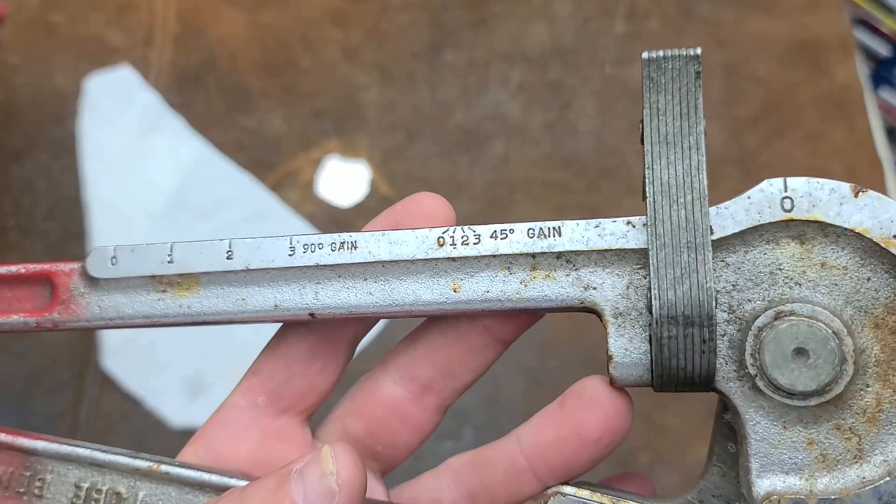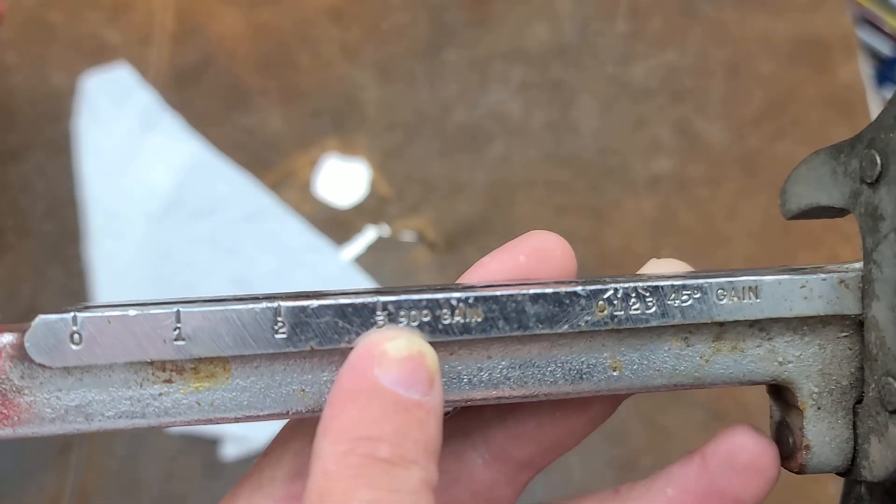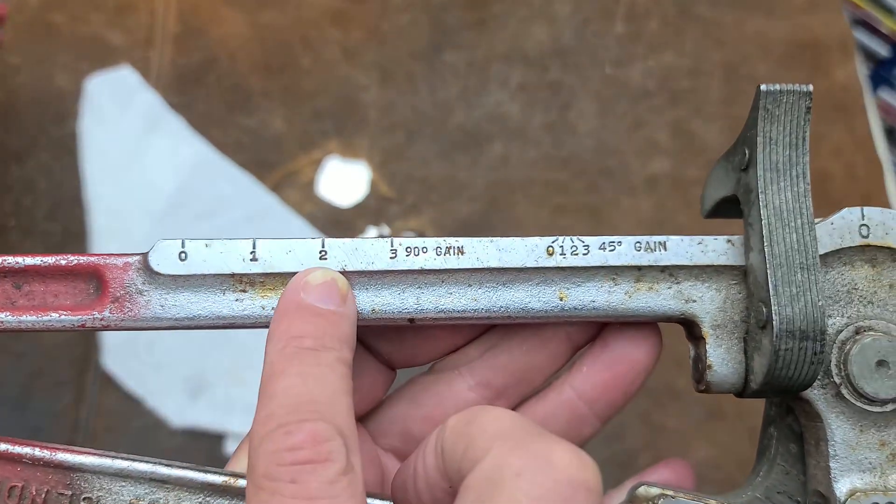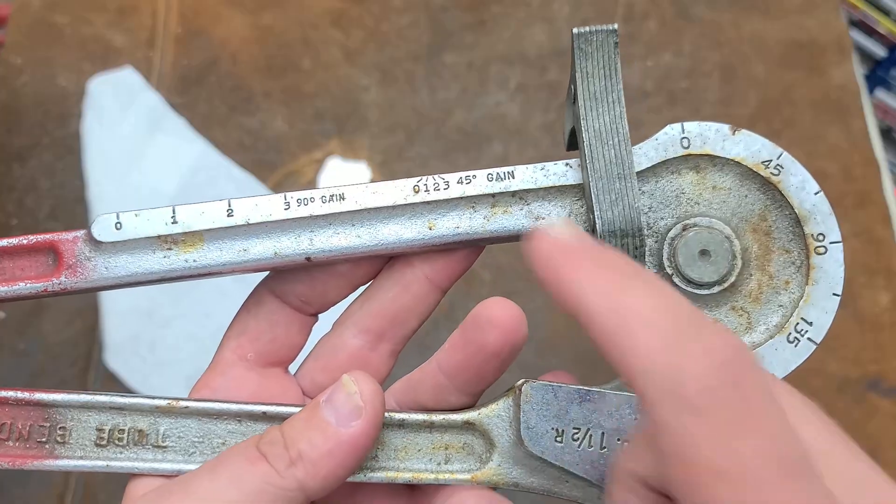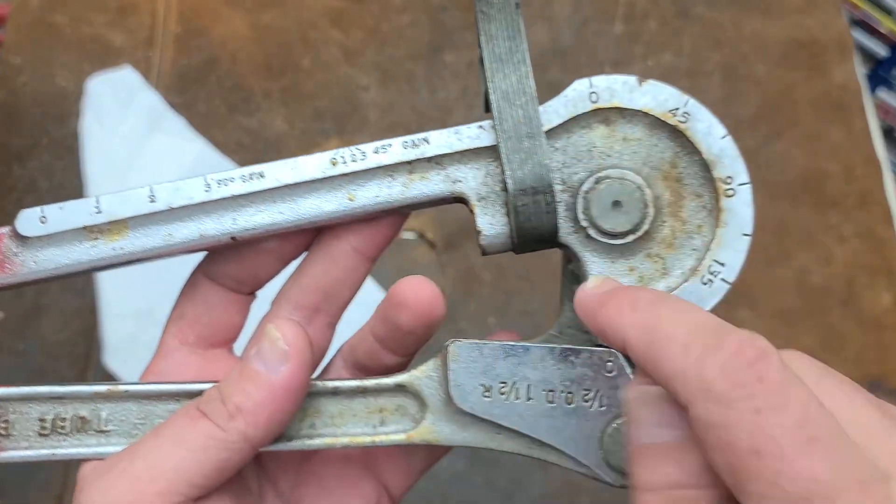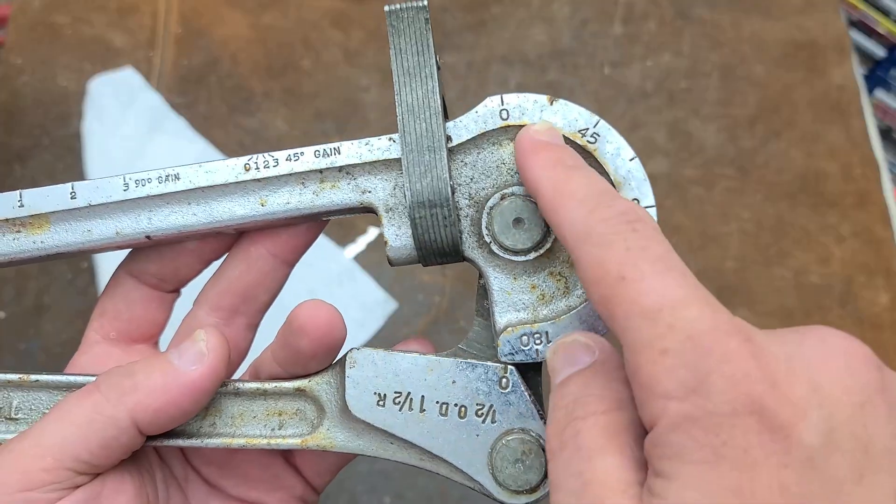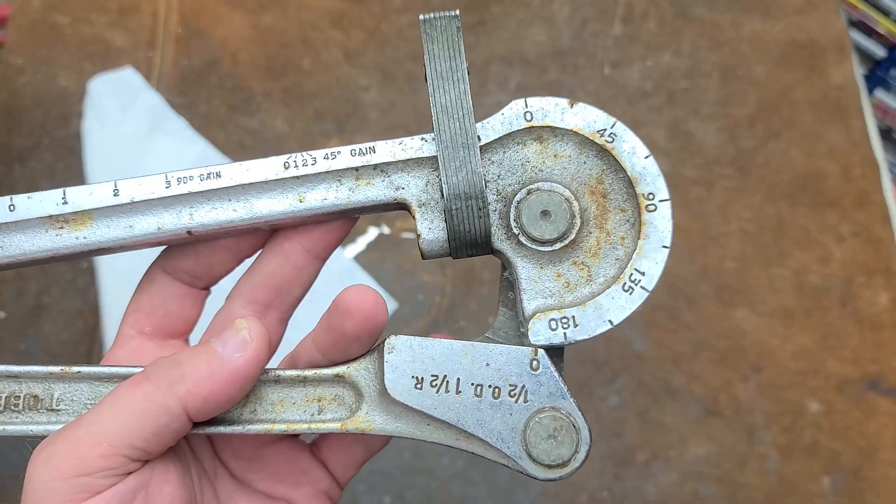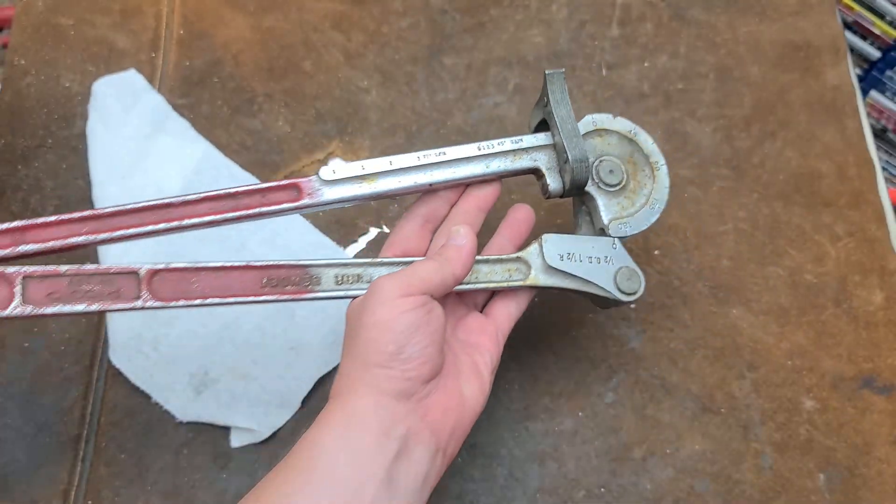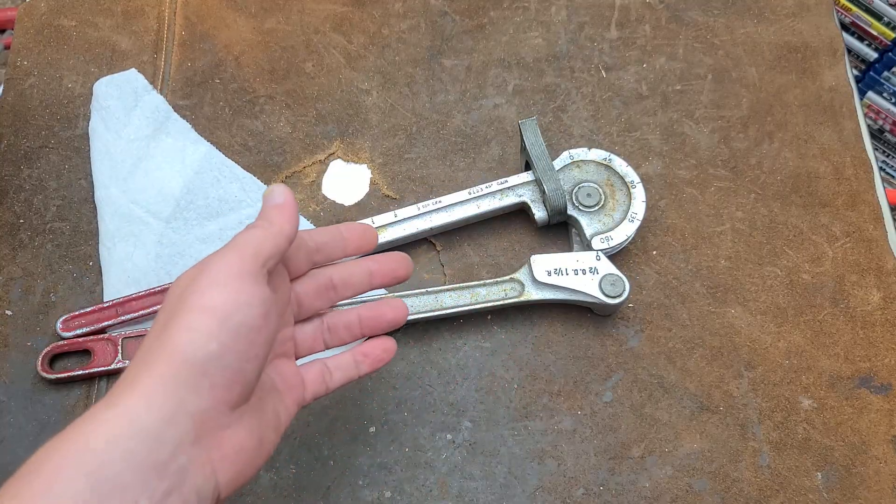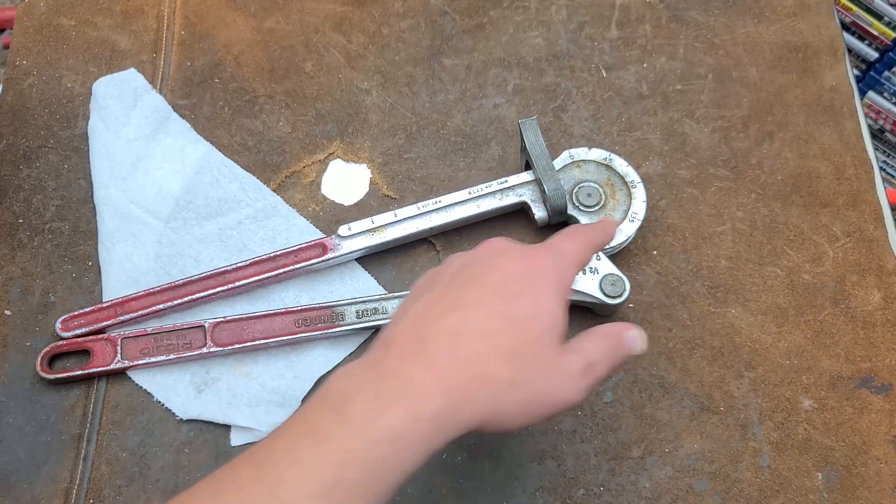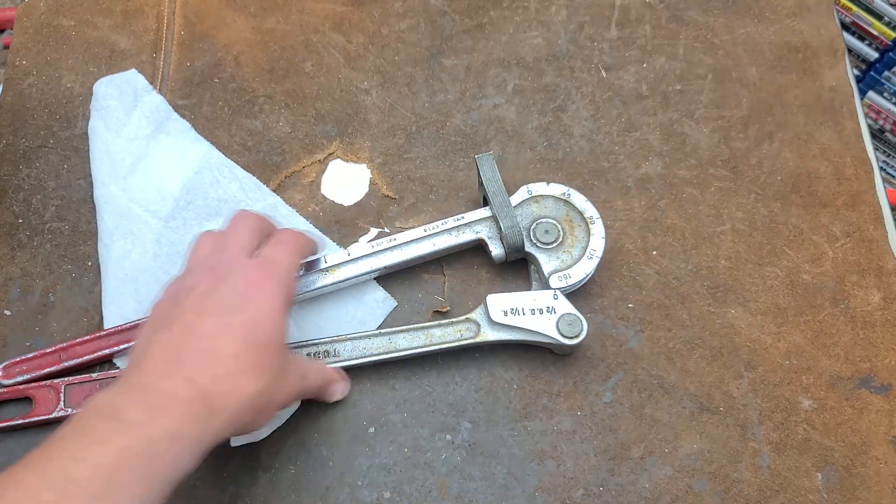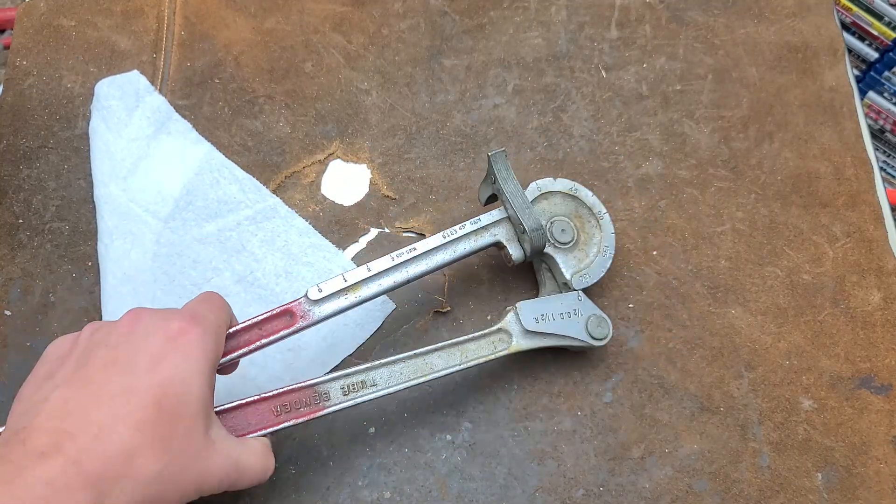The purpose of this scale here, called a gain scale, is so that you can determine how many inches of tubing it's going to take to go around a particular angle, whether it's 45 degrees or 90. This scale is there to help you just make that determination so you can compensate for the length of the arc itself.